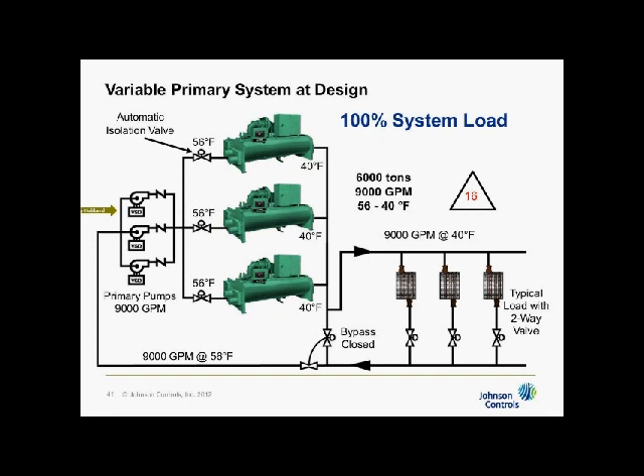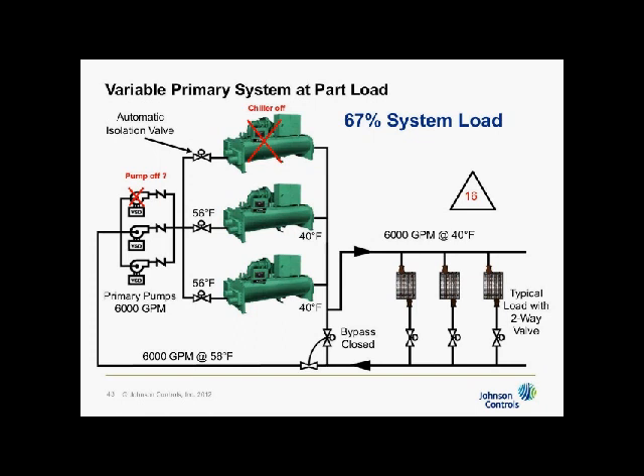We have 9,000 GPM going in our total one circuit, 6,000 tons, designed at 56 to 40. When I go to 75% load, I still have a 16-degree delta T, and if I'm ideal, I have my 6750 GPM, 75% of 9,000, and everything's fine. When I go to 67% load, when I'm under ideal conditions, I can now, at 67%, shut a chiller off because my capacity with two chillers is 67% for the system. So I can turn off a chiller. I can choose to turn a pump off or not. Depends upon whether it's more efficient to run 3 versus 2.